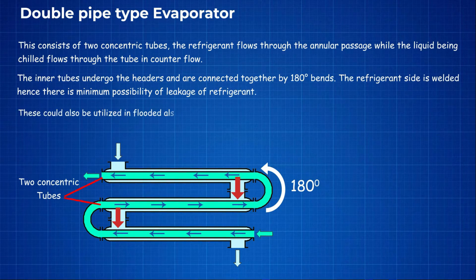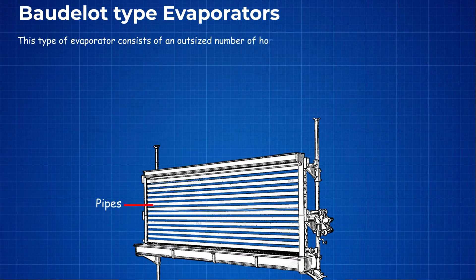These could also be utilized in flooded as well as dry mode. This type needs more room than other designs, but shorter tubes and counterflow give a good heat transfer coefficient. Baudelot type evaporators consist of a large number of horizontal pipes stacked one on top of the other.